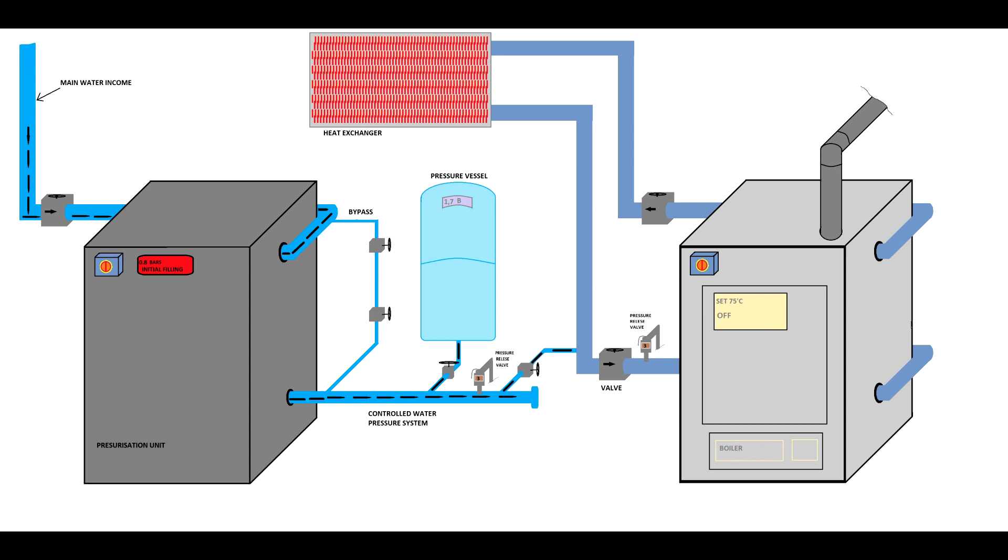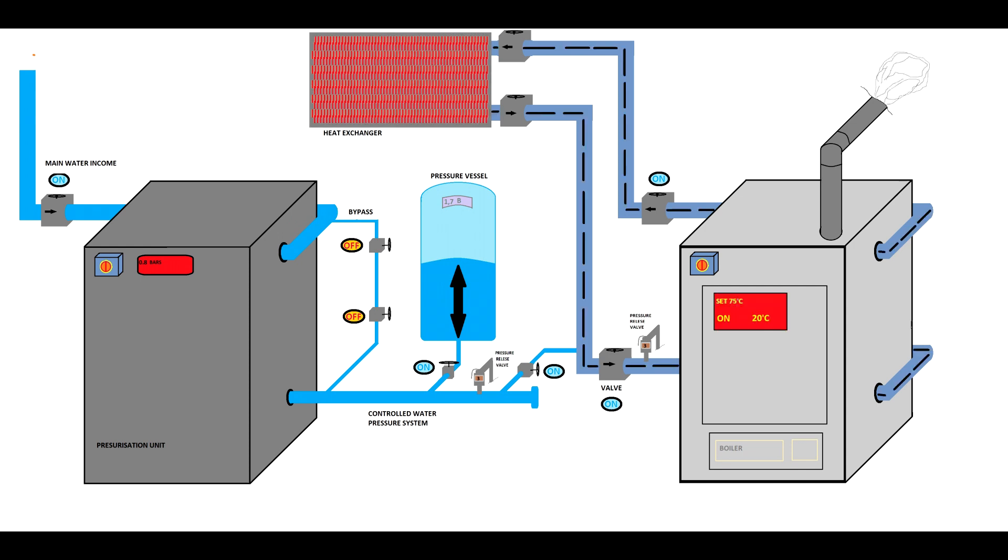The pressurization will push water into the system until it reaches minimum pressure, which is set by you. I usually set it at 0.5 to 0.8 bars. Once the pressure reaches the parameter set by you, the boiler will start working.